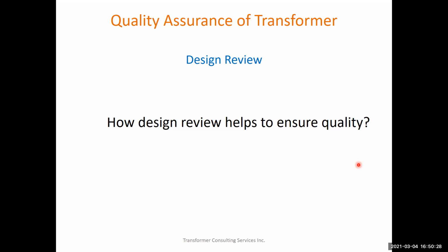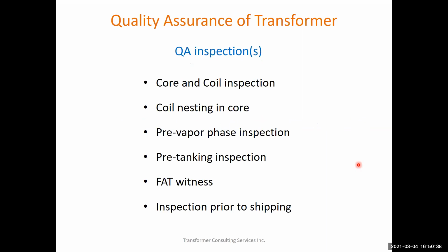And further, to ensure what the transformer manufacturer promised at the design stage has been implemented into the manufacturing process, we do quality control inspection. We do core and coil inspection, coil nesting inspection in the core, pre-vapor phase fitting inspection, pre-tanking inspection, inspection during the factory acceptance test, and inspection prior to shipping.